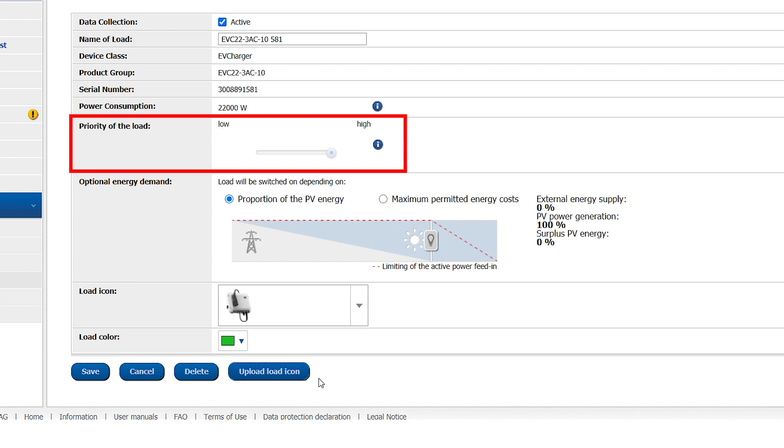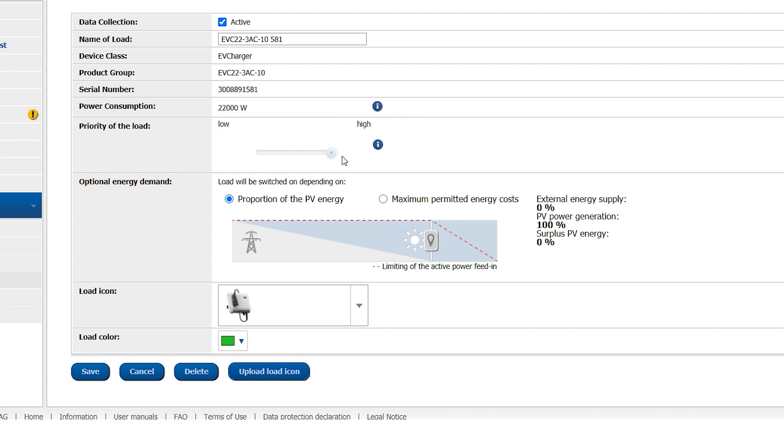So setting the SMA EV Charger to High Priority and a second device to Low Priority means the Sunny Home Manager 2.0 will only switch on this lower priority device once more power than the SMA EV Charger can use is available.